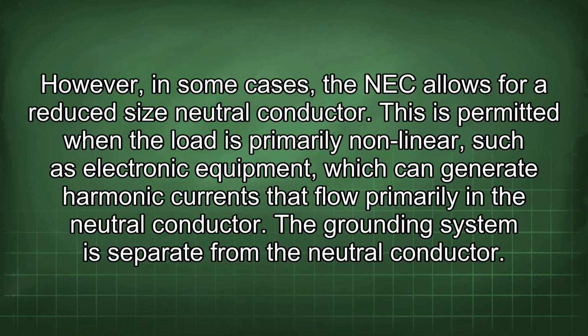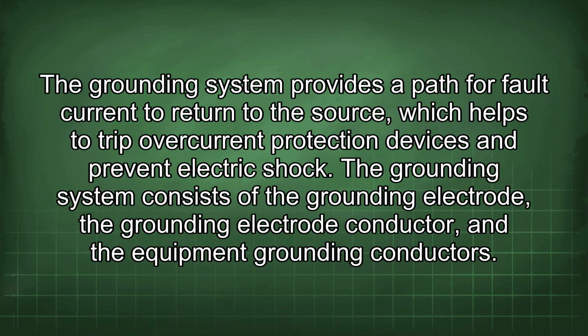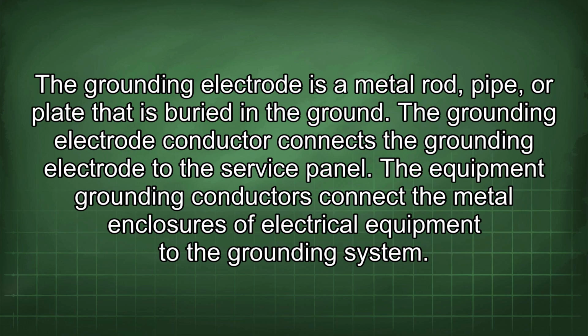The grounding system is separate from the neutral conductor. The grounding system provides a path for fault current to return to the source, which helps to trip overcurrent protection devices and prevent electric shock. The grounding system consists of the grounding electrode, the grounding electrode conductor, and the equipment grounding conductors. The grounding electrode is a metal rod, pipe, or plate that is buried in the ground. The grounding electrode conductor connects the grounding electrode to the service panel. The equipment grounding conductors connect the metal enclosures of electrical equipment to the grounding system.